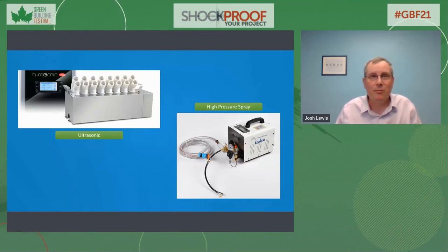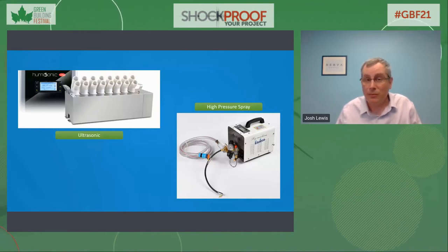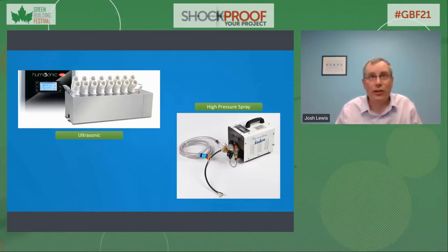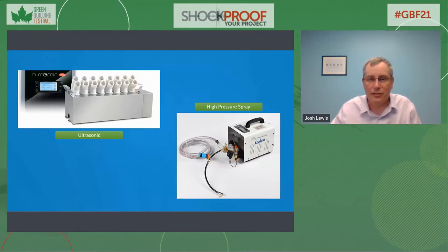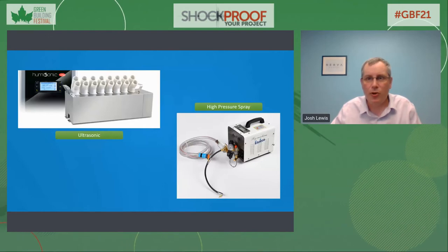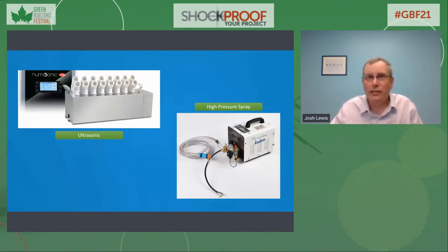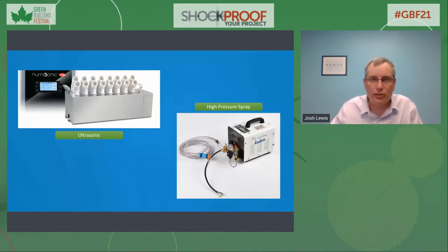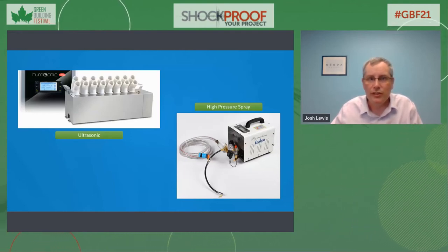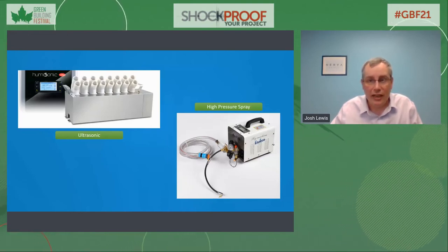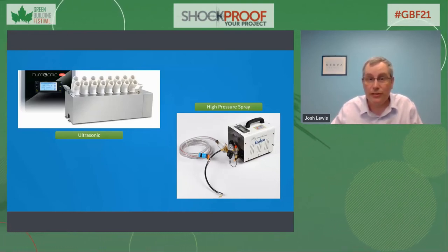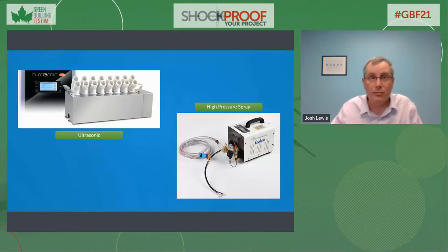Humidity injection systems must be installed into HVAC systems. In the past, these systems were typically steam-based, but those are now considered obsolete due to their high cost and extensive maintenance requirements, also excessive energy use, except in hospitals where they're still required by code. Newer humidity systems are typically based on either ultrasonic or high pressure spray technologies. Regardless of what type is chosen, there will be installation, energy, and maintenance costs associated with it that are above and beyond the requirements of the building code in order to create a healthy environment.